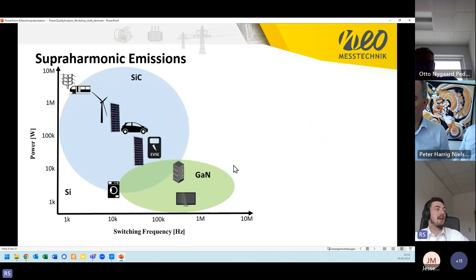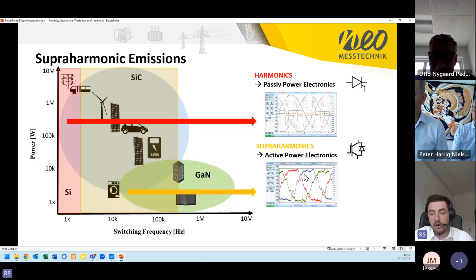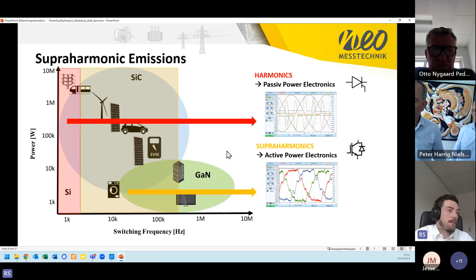With the new silicon carbide technology in MOSFETs and IGBTs, we see active power electronics more and more in our grid. In the current waveform, it's getting more sinusoidal, but there's a lot of noise actually. This is why we do this, we want to get more efficient, that's the main reason for switching to this technology. We get more efficient, but on the other hand we get high frequency components, high frequency supraharmonic emissions in our grid. So what are the effects of supraharmonics in our grid?